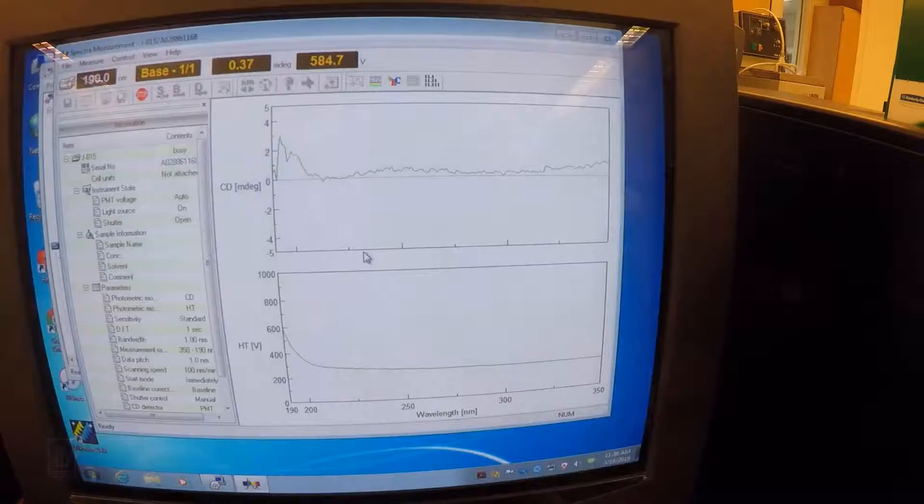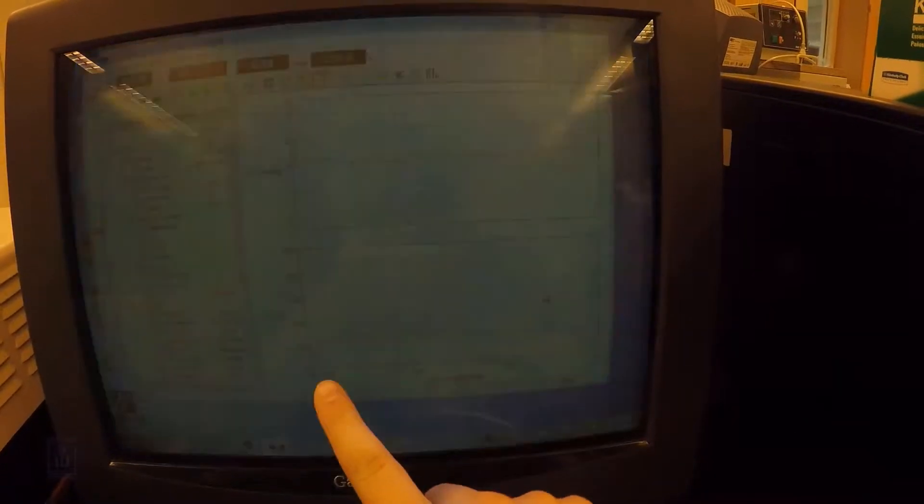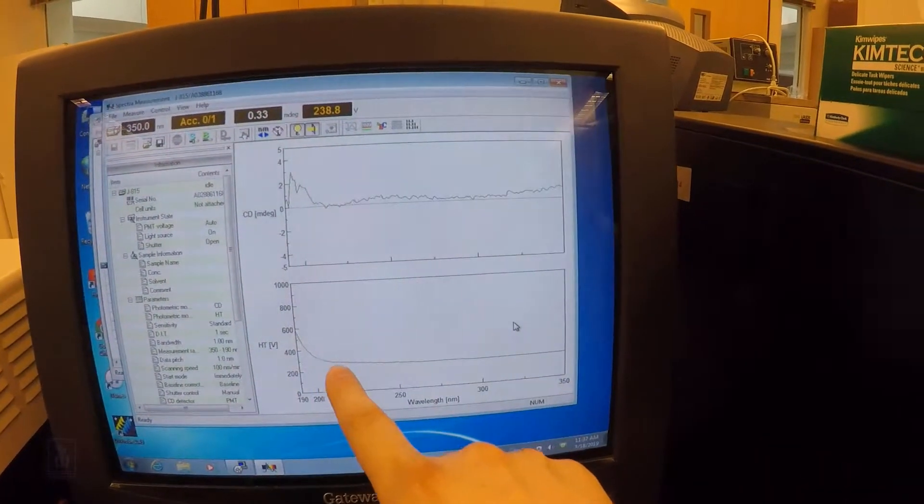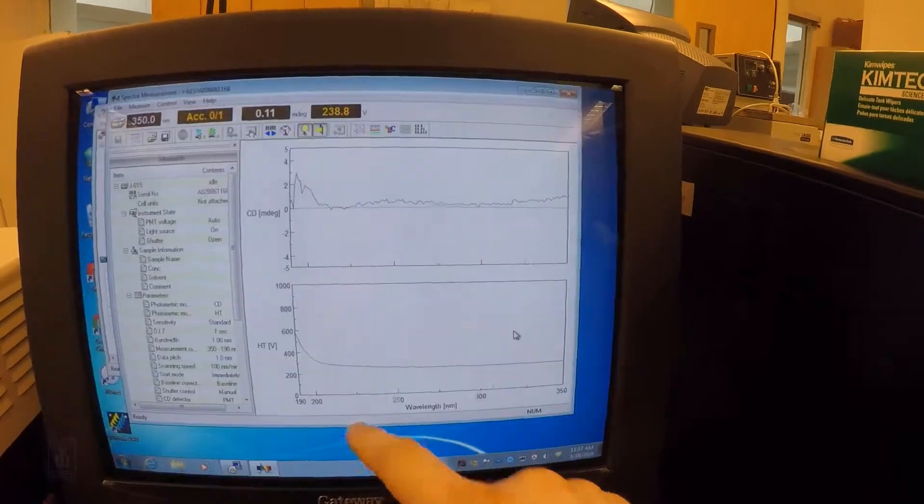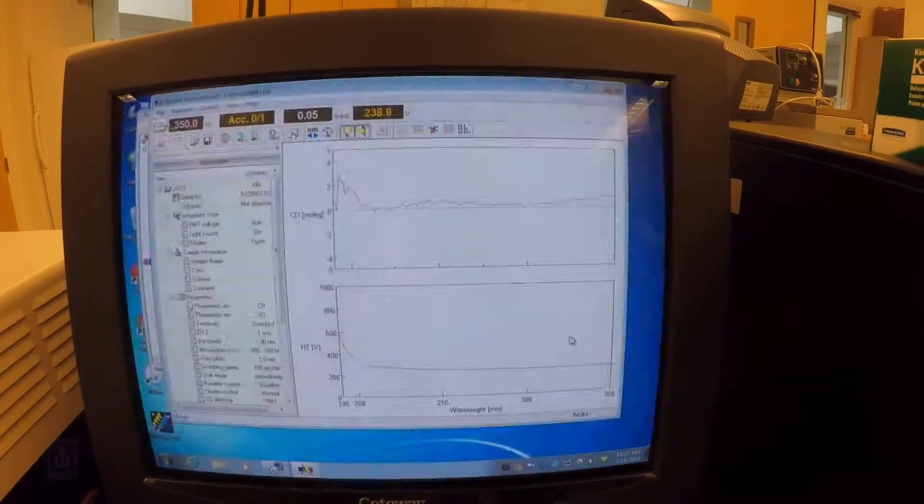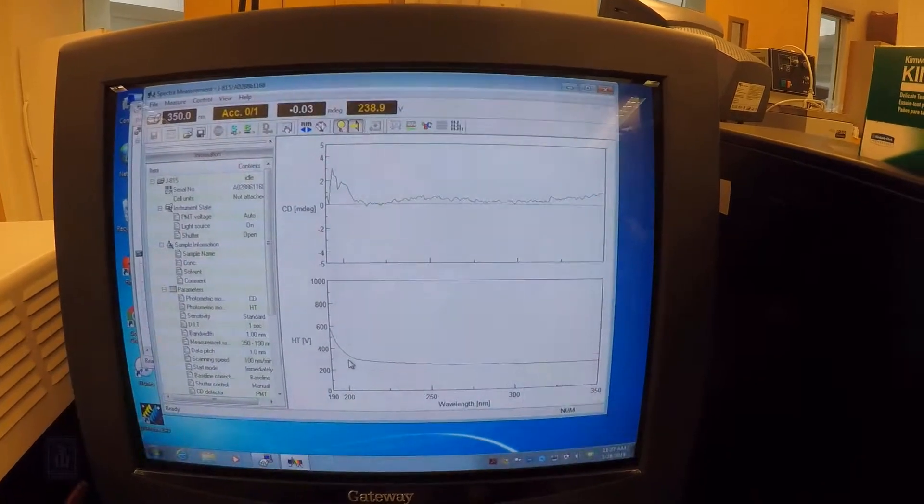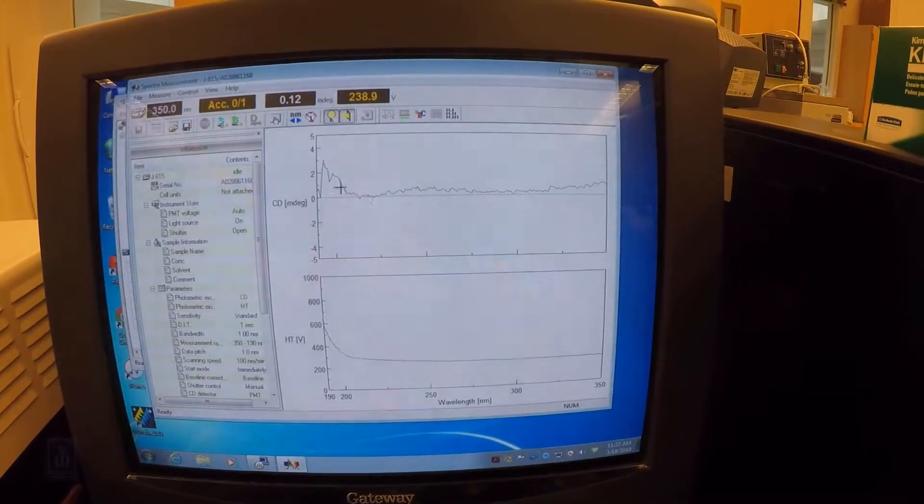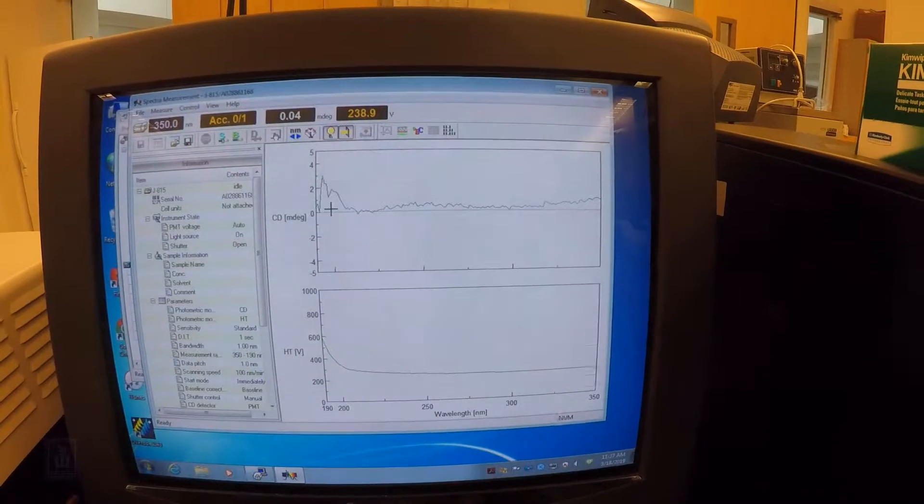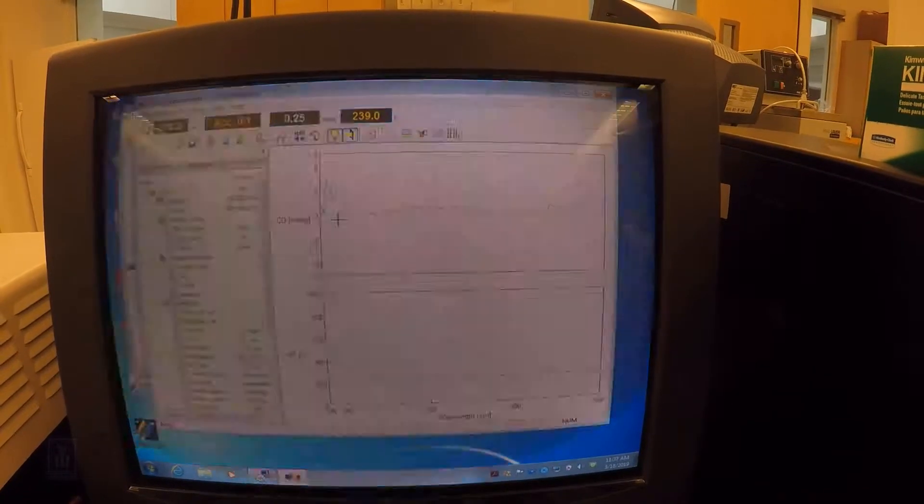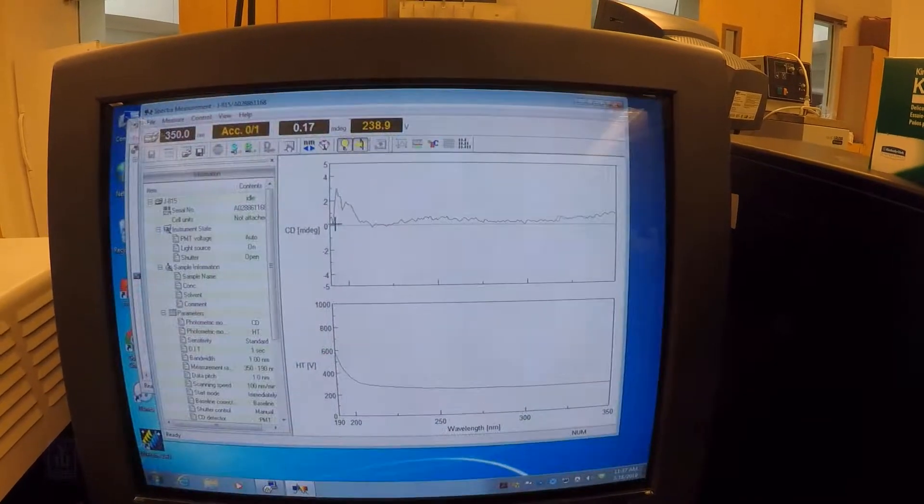What we can see here from our blank spectrum is largely a flat line. Down here on the HT, which is our voltage on our photomultiplier tube, you can see it's pretty flat until it gets down here to about 200 when it starts to really ramp up. That's where oxygen is starting to absorb some of the photons and steal them from the photomultiplier tube. And so we need to turn up the gain so that more hits the actual detector. You should expect that when you do a scan. You also should expect maybe a little bit of circular dichroism as that gain gets turned up, as the noise gets amplified, but largely there's nothing happening here. So next step is to load your sample.